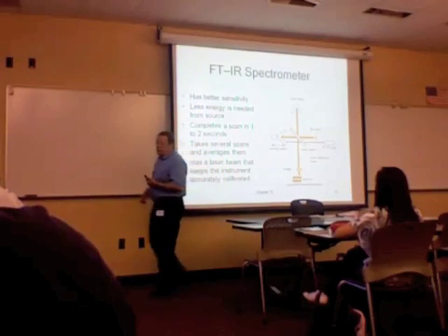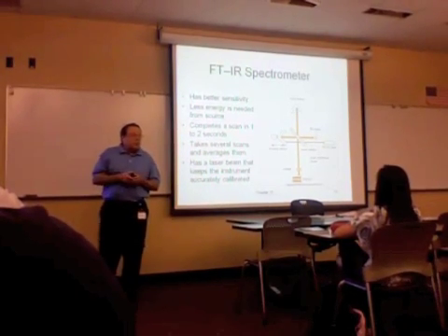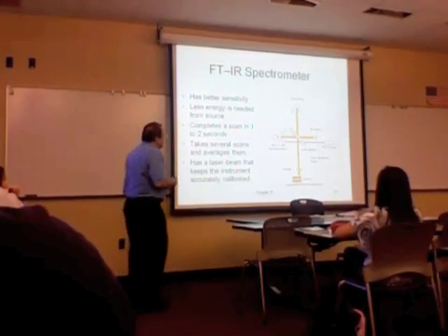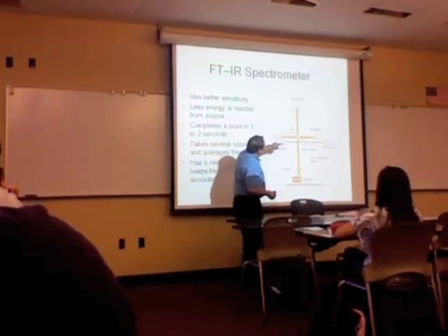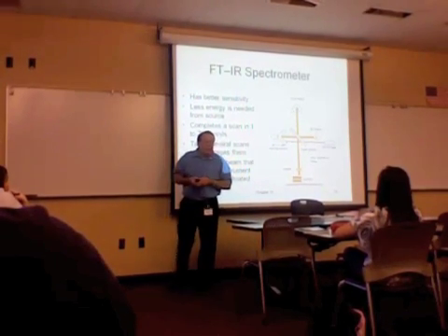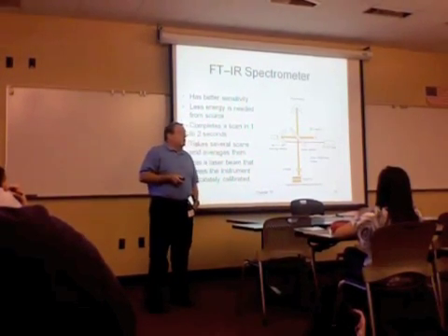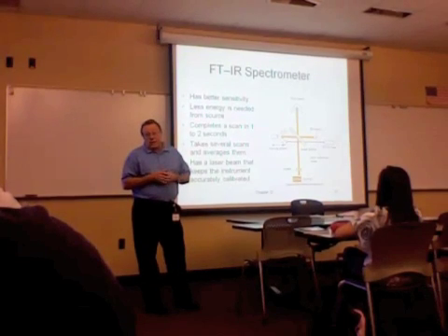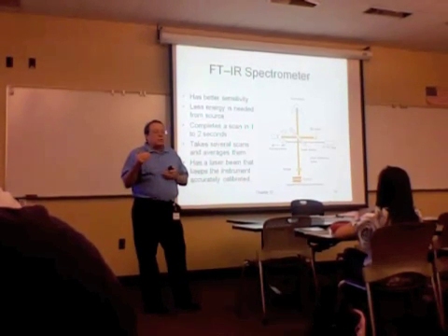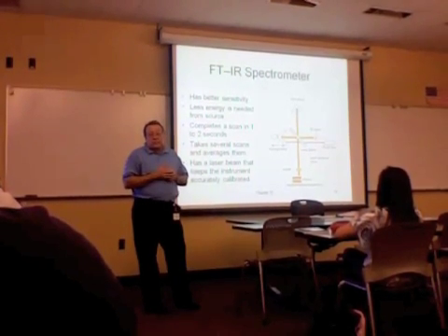And a laser beam is bouncing off of the same optical path or mirrors and so forth that the sample is, and this is used to focus or automatically self-calibrate the optics. So you don't have to go in and do a lot of adjustments. Now we still occasionally have to go in and do some adjustments and some repair, but the instrument is able to detect the intensity of the laser beam.